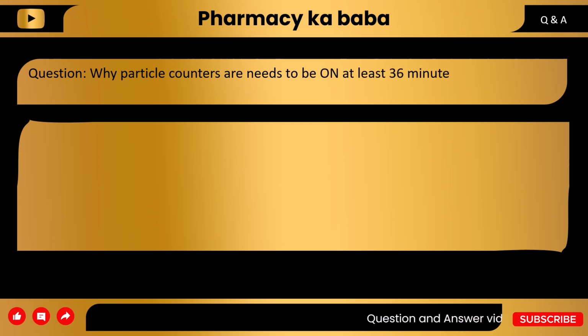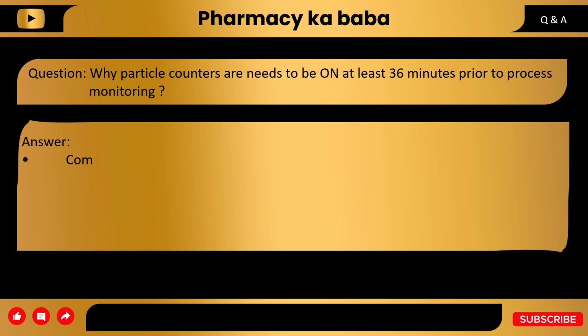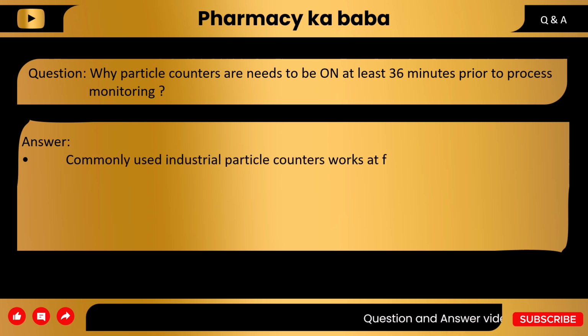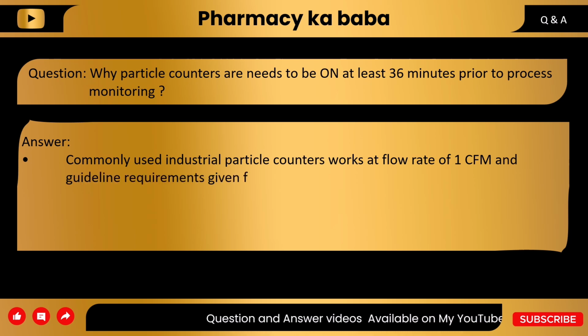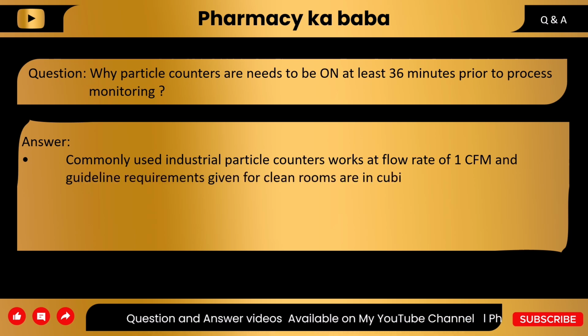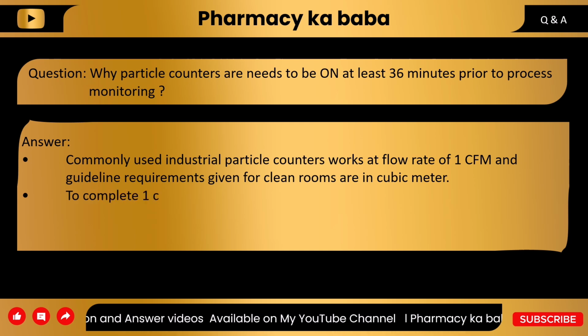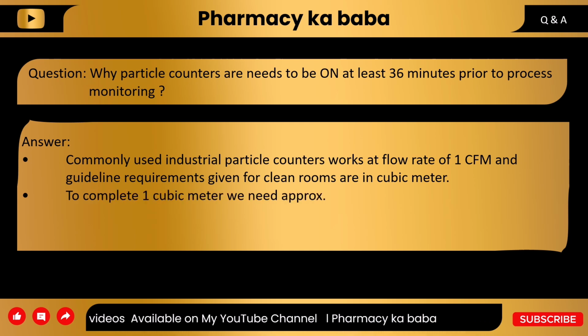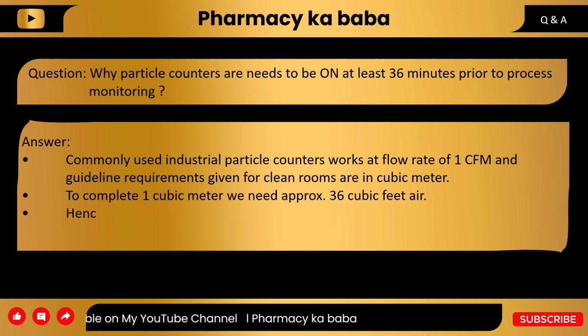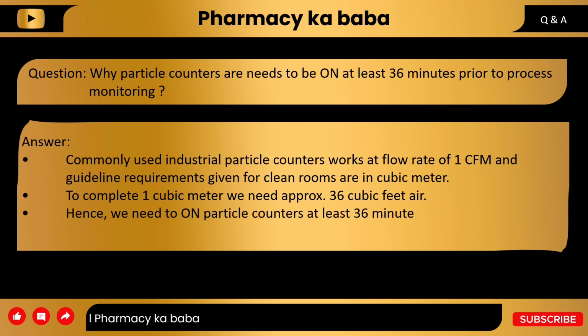Question. Why does the particle counter need to be on for at least 36 minutes prior to process monitoring? Answer. Commonly used industrial particle counters work at a flow rate of 1 CFM, and the guideline requirements for clean rooms are in cubic meters. To complete 1 cubic meter, we need approximately 36 cubic feet of air. Hence, we need to run the particle counter at least 36 minutes prior to process monitoring.